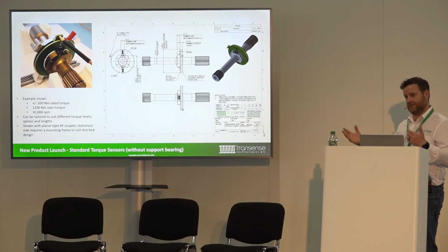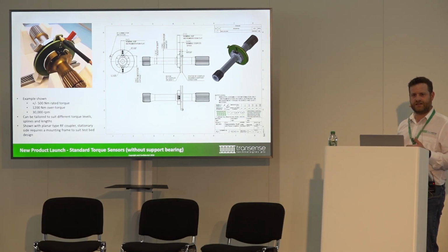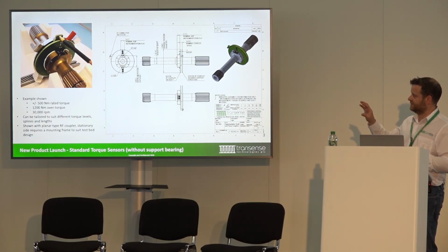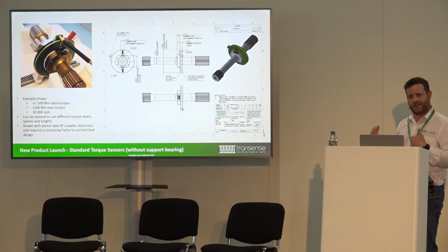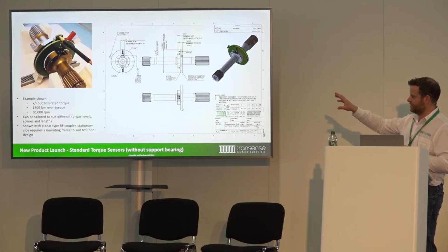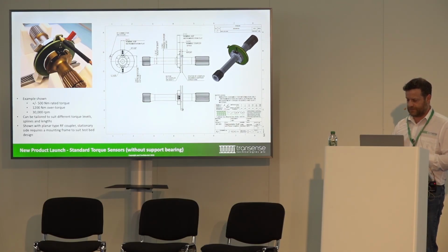They subsequently upgraded all of their dyno test rigs - there are about 10 or 15 dyno test rigs in their facility, so quite a large motor testing facility. It's enabled them to do these high-speed, high-dynamic test cycles without seeing torsional vibration coming through and corrupting their data. So it's been a really good example, and now we can offer the same concept to other people.